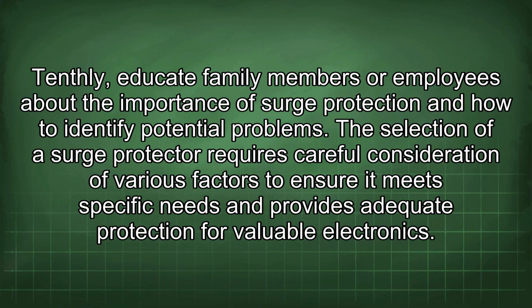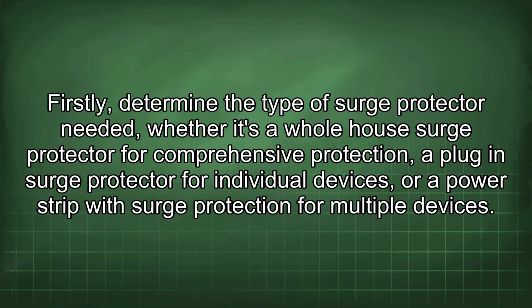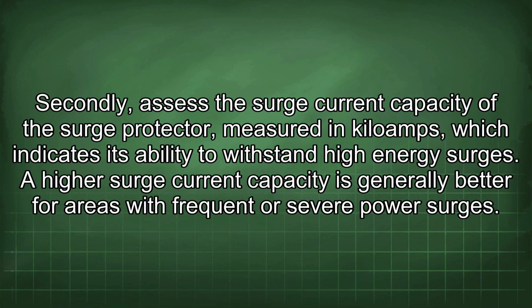The selection of a surge protector requires careful consideration of various factors to ensure it meets specific needs and provides adequate protection for valuable electronics. Firstly, determine the type of surge protector needed, whether it's a whole-house surge protector for comprehensive protection, a plug-in surge protector for individual devices, or a power strip with surge protection for multiple devices. Secondly, assess the surge current capacity of the surge protector, measured in kiloamps, which indicates its ability to withstand high energy surges.